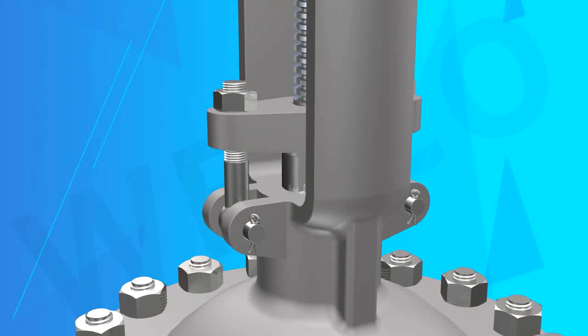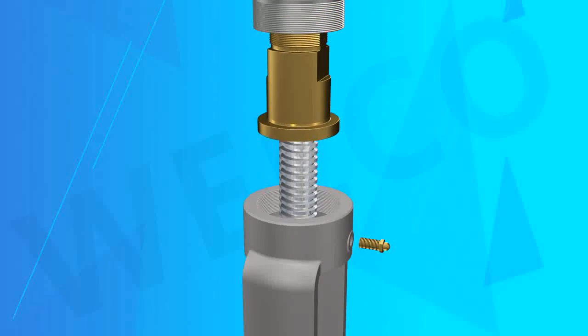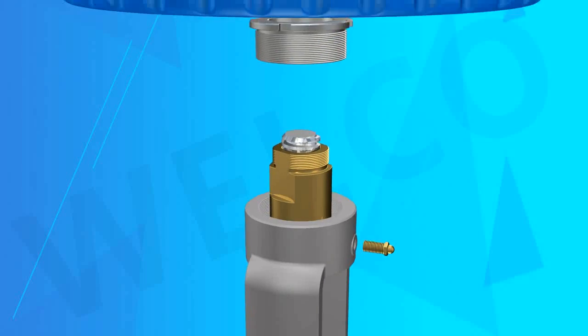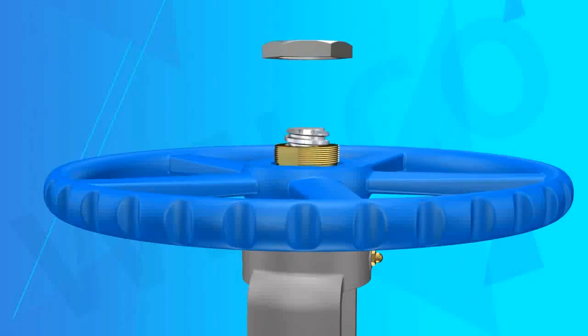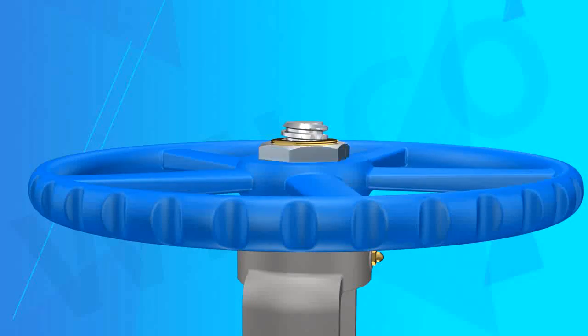4. Disc design - 2 inches and below can use solid gate. If size larger than 2 inches can be flexible wedge. It can also be used according to requirements of flat plate or double gate plate structure.